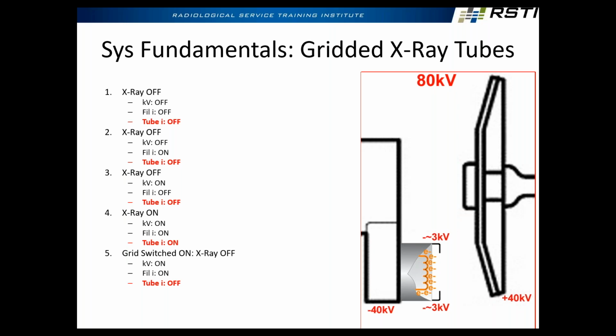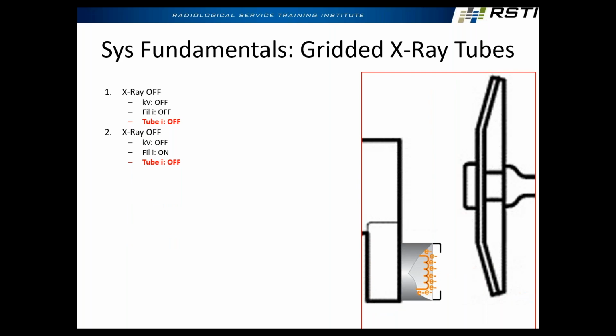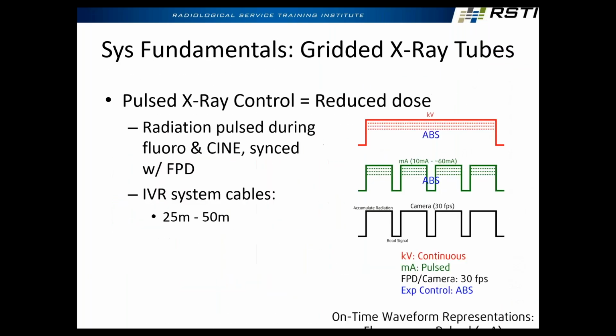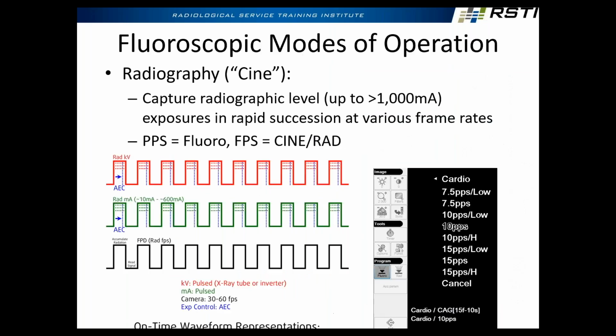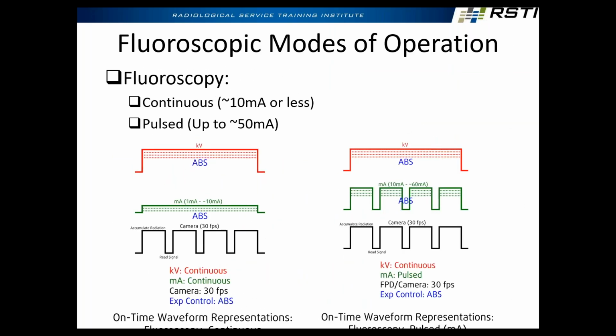This is a little advanced for this class, but for an introduction, with cath and angio, we were talking about the detectors. So you know how we said a minute ago that cameras can't capture full time? So why is continuous radiation a bad thing? Here's my detector. It's only capturing at a certain frame rate. If I'm producing radiation the whole time, any problems with that? The patient is getting radiation, which is not being seen or used by the detector. Does that make sense? So that's continuous MA.